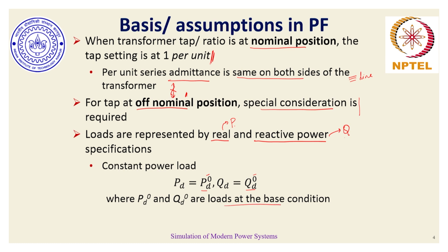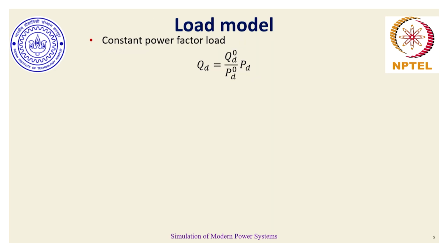As electrical engineers, you can also think of, do we actually have such loads which can be represented by constant power load? It's an interesting question, please think about it. To the best of my experience and understanding, we rarely have any such load which maintains its constant power consumption. And hence, this is one of the most idealistic conditions of representing a load entity in terms of real and reactive power. What is more practical than this idealistic condition is that there are loads where they tend to maintain their power factor.